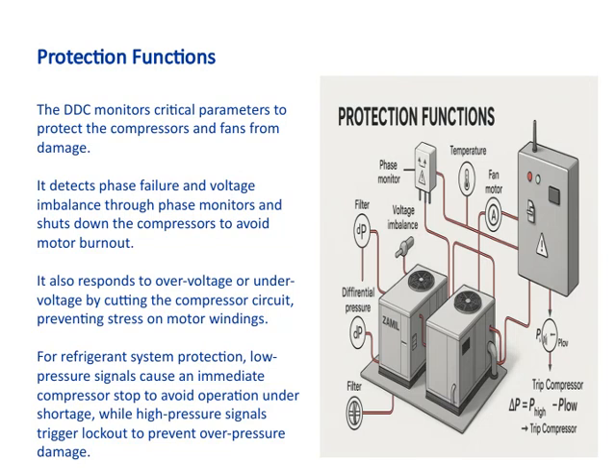In this slide, we're focusing on the protection functions of the DDC, which are crucial for safeguarding the equipment. The DDC constantly monitors key parameters to prevent damage to compressors and fans. For example, it detects phase failure and voltage imbalance using phase monitors, and if these issues are identified, it will shut down the compressors to avoid motor burnout. It also responds to electrical issues like overvoltage or undervoltage by cutting the compressor circuit, which helps prevent stress and potential failure of the motor windings.